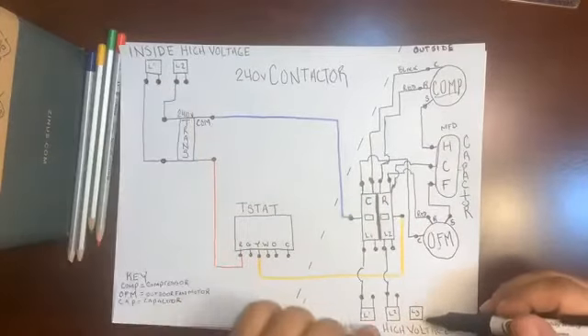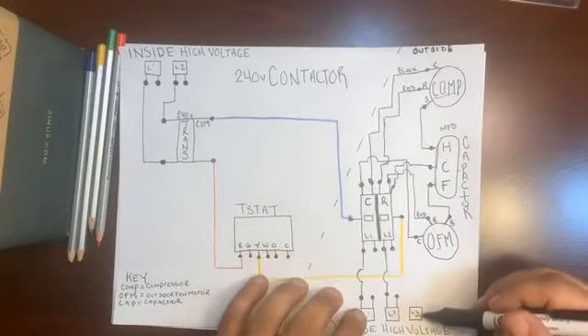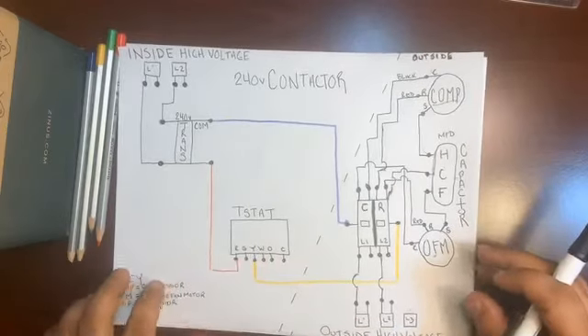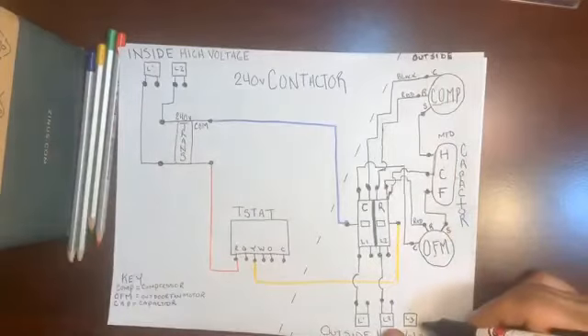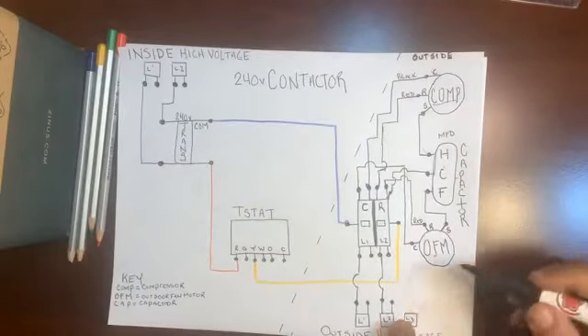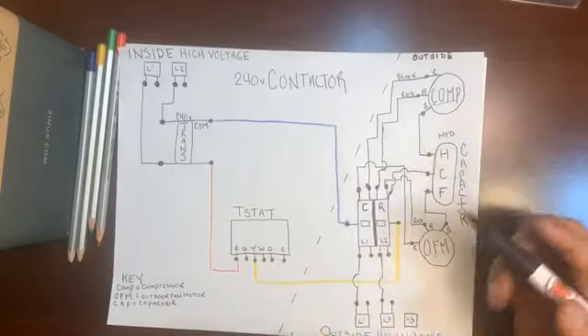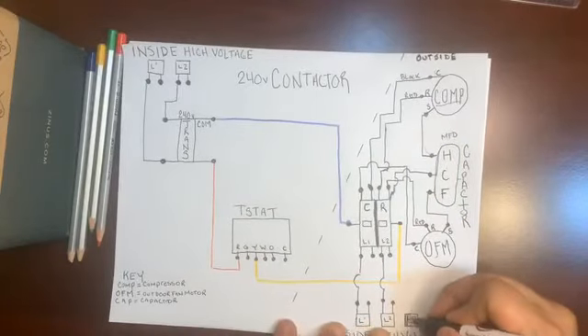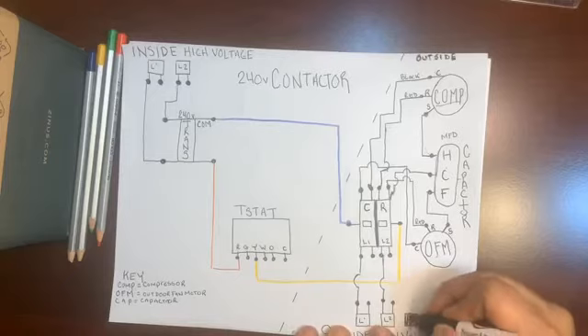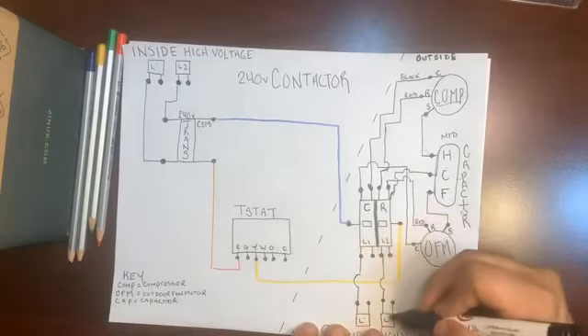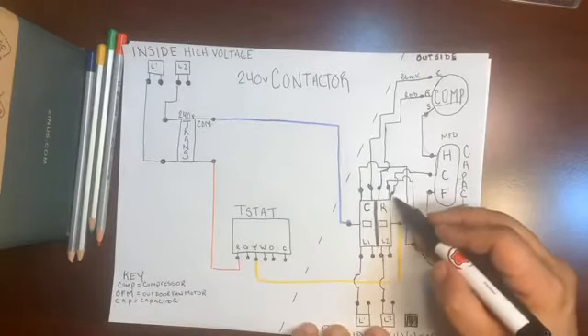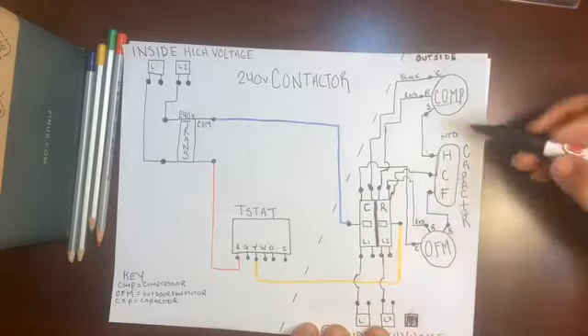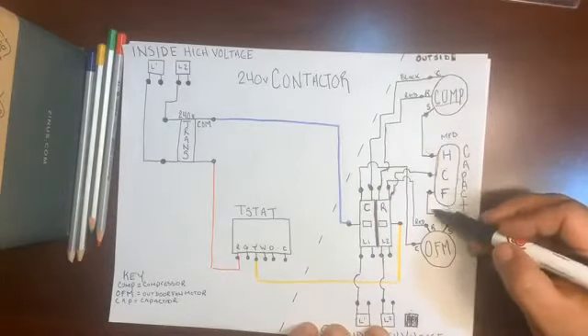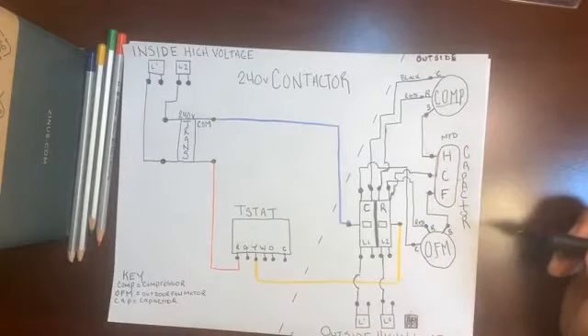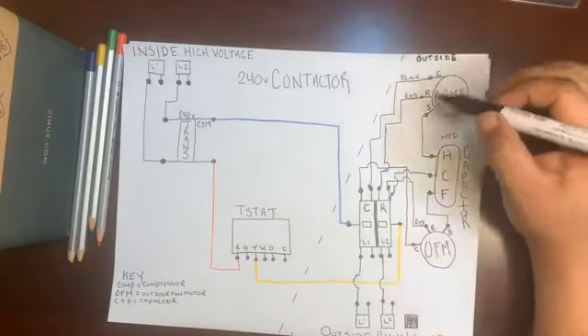240 will hurt you. 330, 360, this will really do some damage. So that's, again, another benefit of staying in the residential side of the business, because in the commercial, you're going to be dealing with L3. But again, you have L3, and then you won't have capacitors. But in our residential systems, we use L1, we use L2, we keep it 2-phase. We run the L2 up into the run, split a wire off to the common of the capacitor, feed the hermetic, feed the fan, and that completes our high voltage for the outside condenser.